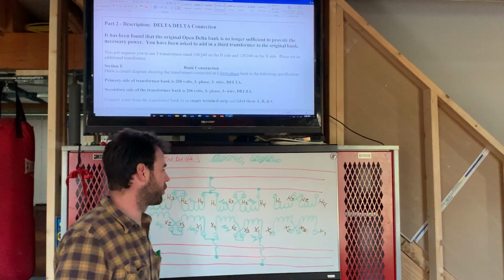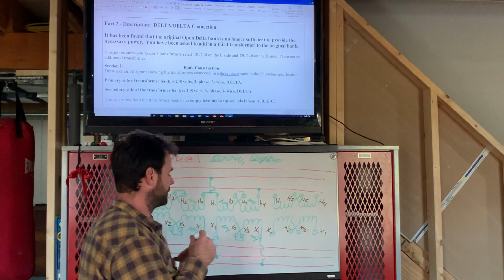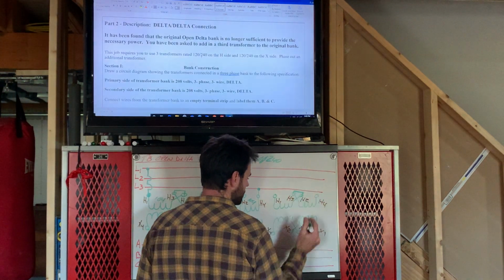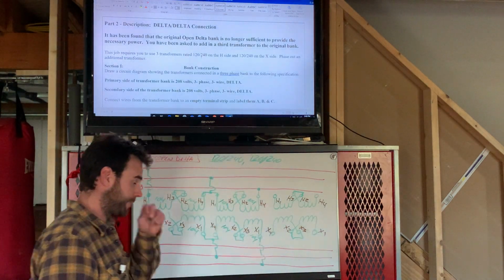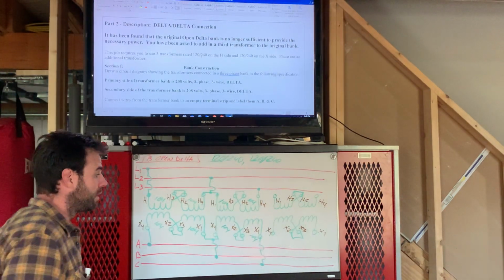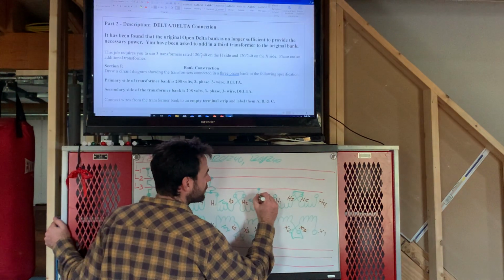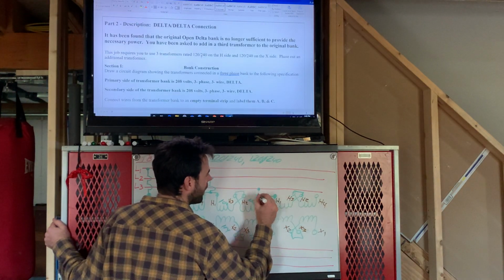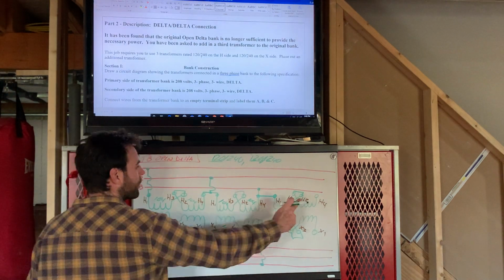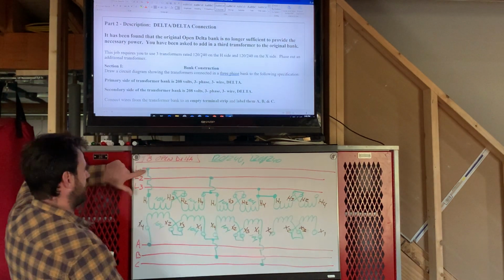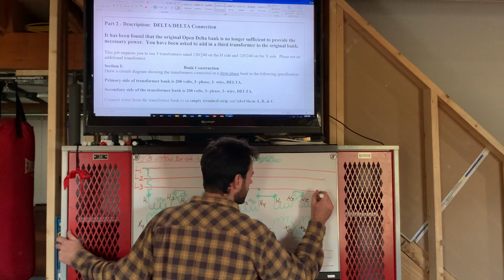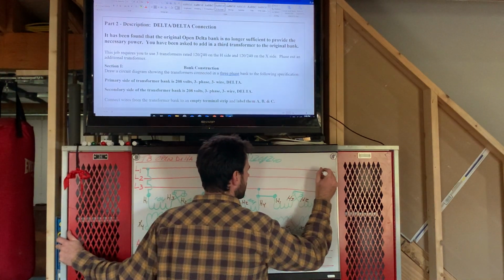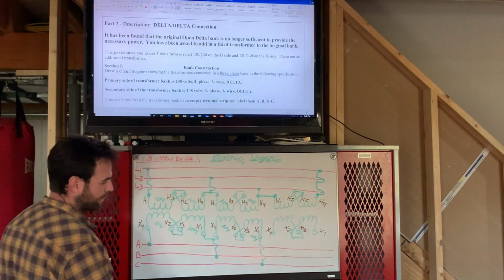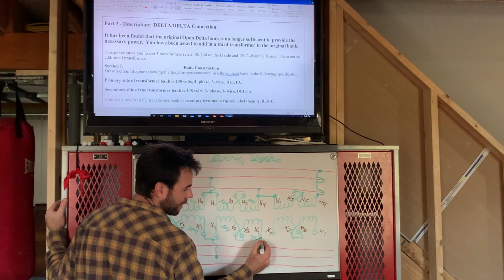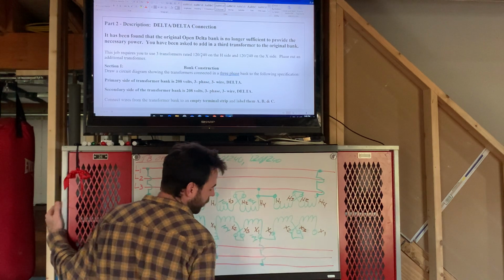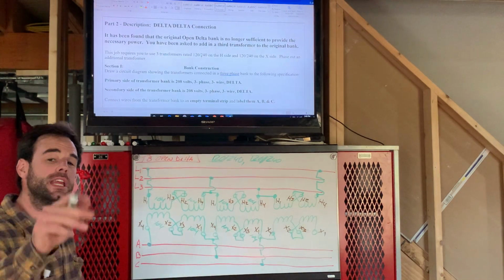Again, we're going to put this transformer in series just like we did with the other ones. So you can go H3 to H2, X2 to X3. Now what we're going to do is jump H4 to H1. And then we're going to bring H4 here up to line 1.